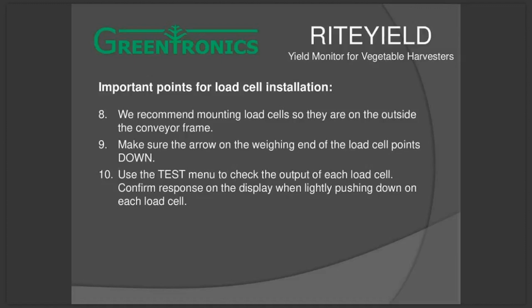And then there's a test menu on the console that you can go to see if you've installed the load cells right and that they're working properly. And those are fairly easy to do. You will see two numbers. They should be reasonably close together to tell you that the load cells are balanced properly. They each see 50% of the weight of the empty conveyor. And you can confirm that they're working properly by just pushing down a little bit on them, and you see the numbers change on screen.